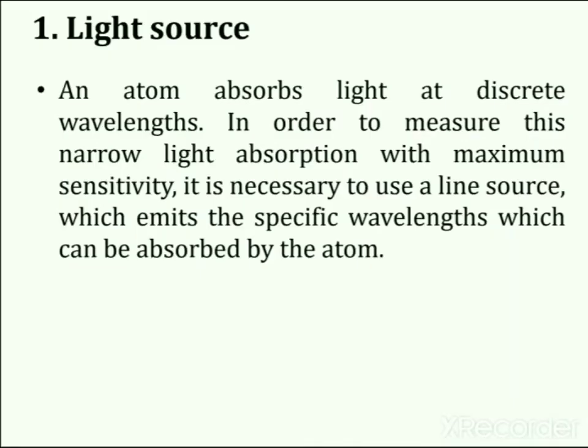The radiation or light source is the first part of the atomic absorption spectrophotometer. An atom absorbs light at discrete wavelengths, so in order to measure this narrow light absorption with maximum sensitivity, it is necessary to use a line source. Line sources emit the specific wavelengths that can be absorbed by the atom, providing high sensitivity and making atomic absorption a very specific analytical technique with few spectral interferences.